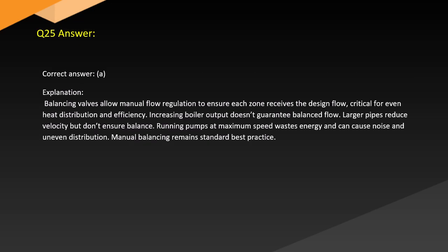Answer. Correct answer, A. Explanation. Balancing valves allow manual flow regulation to ensure each zone receives the designed flow, critical for even heat distribution and efficiency. Increasing boiler output doesn't guarantee balanced flow. Larger pipes reduce velocity but don't ensure balance. Running pumps at maximum speed wastes energy and can cause noise and uneven distribution. Manual balancing remains standard best practice.